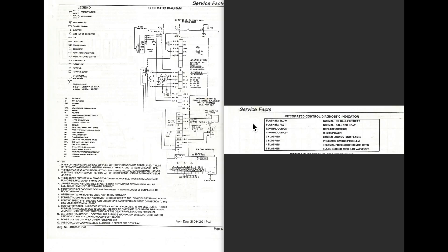Okay, so let's go over these lights right quick. Flashing slow simply means normal, no call for heat. That means the power's there, and it's ready for a call for heat. Flashing fast means normal with a call for heat. So we're actually calling for heat.